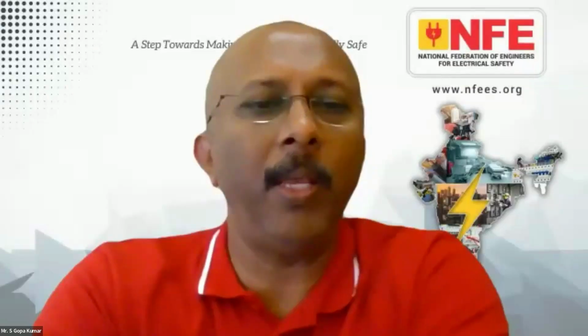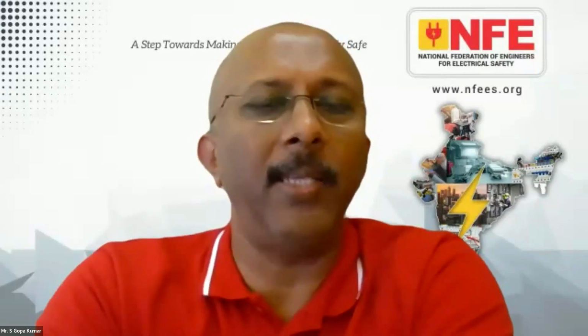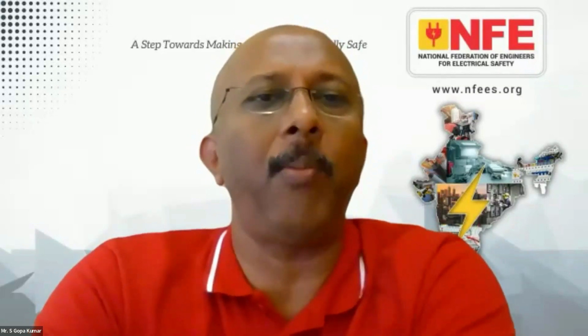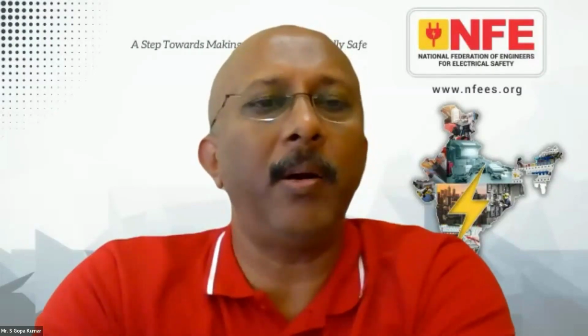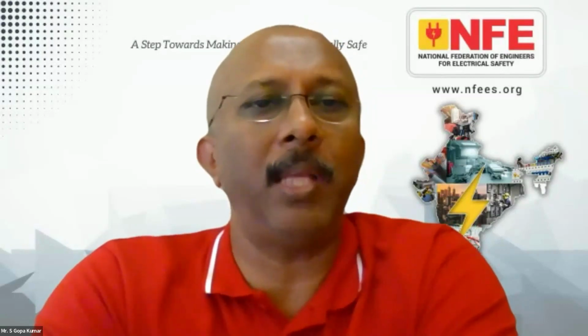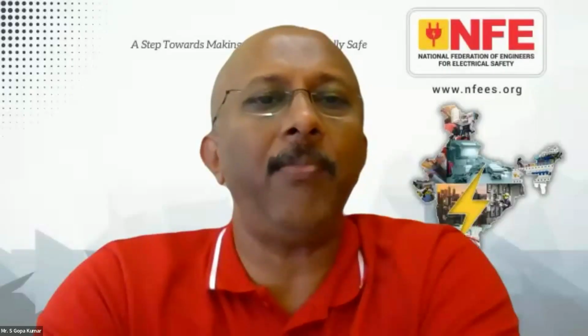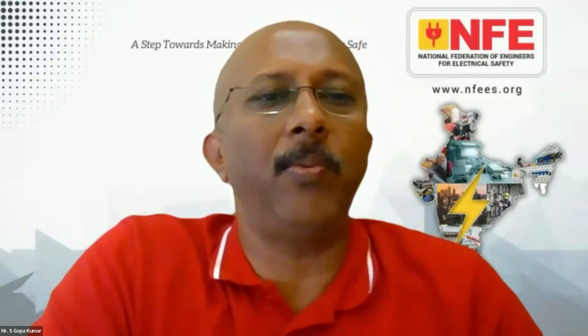Normally in other countries, when we go for these IEC meetings, harmonics is not a big subject of discussion with respect to the point of common coupling, or as far as the distribution or transmission company is concerned. I had a few discussions with some of them, and what I understood is that finally the connected equipment or electrical appliance is creating harmonics. In those countries, the amount of harmonics which these devices generate has to have a certain limit. That means at the source itself, the harmonic generation is limited. Once the harmonic generation itself is limited, the effect of this harmonic on the entire network is also automatically reduced.